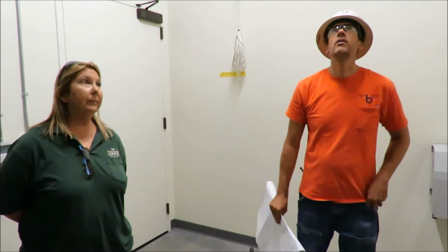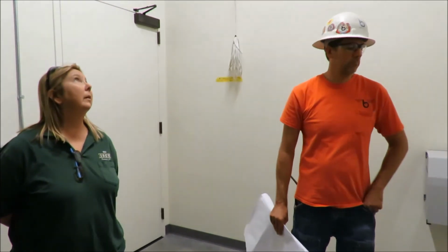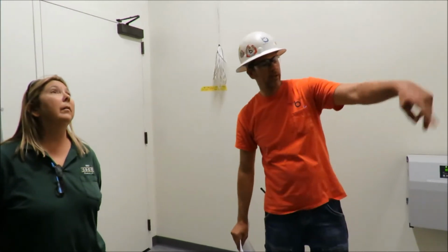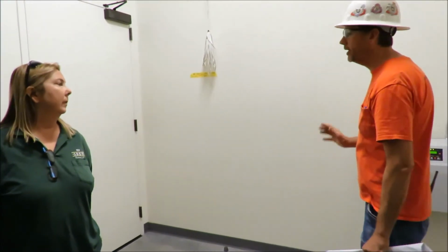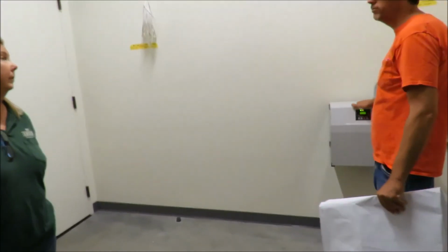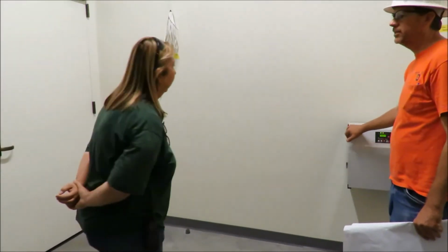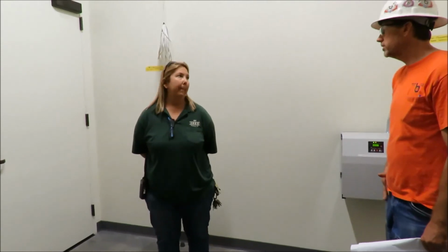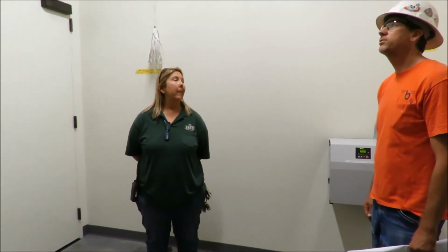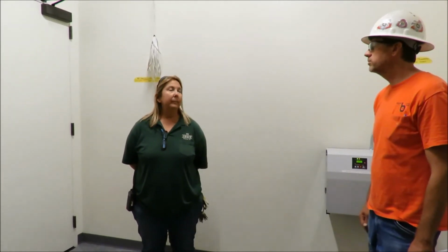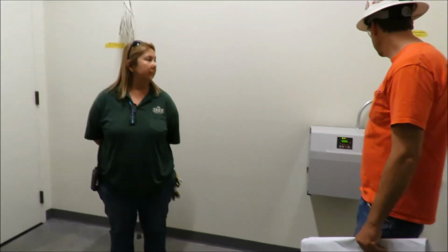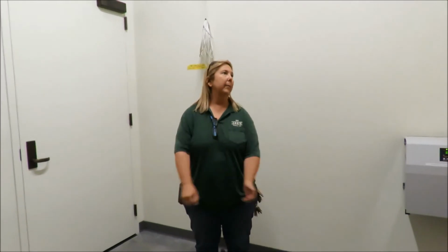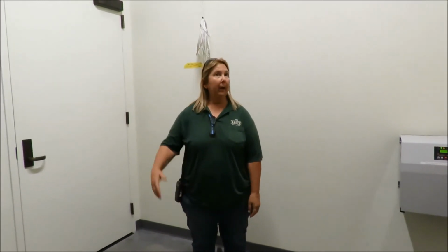Thank you. So yeah, we're adding some smoke detectors right now. That's what that red pipe is, because I guess I didn't know, but as soon as you have batteries inside the room you need a smoke detector, and it wasn't shown on the print, so it was overlooked by everybody. So right now we're in the process of adding that. It's probably smart. We've had some incidents with some other inverters that now are ripped out.